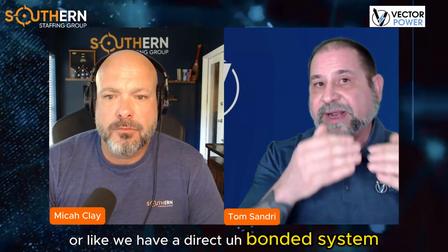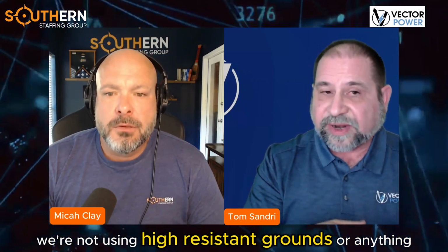Gotcha. And so one of the ramifications, let's say I'm testing a cable, or I haven't even tested it yet. I have excessive partial discharge. How does that affect the end state equipment? Initially it's not going to have an effect on the end state equipment, but if it goes to fault and all of a sudden we have a discharge of maximum fault current, this obviously is going to put stress on the associated apparatus, if the protection equipment doesn't clear in its prescribed periods of time and so forth. Or like we have a direct bonded system. We're not using high resistive grounds or anything. Your transformers and so forth are going to take quite a jolt. Gotcha. Okay, that makes sense.